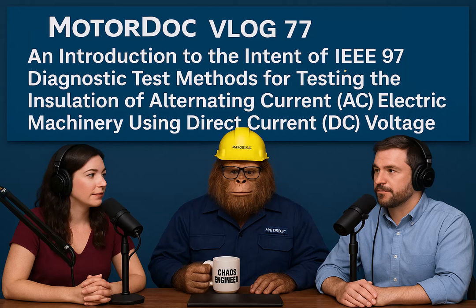They provide an example illustrating this effect of thermal aging making the IRP look straighter. Interesting. Finally, uncured insulation. What does that look like on an IRP? You mentioned it was risky. Right. Uncured varnish or resin, it tends to polarize faster than fully cured material. A bit like moisture does, actually. So the shape is similar to moisture. Yeah, it makes the IRP shape resemble that caused by moisture.